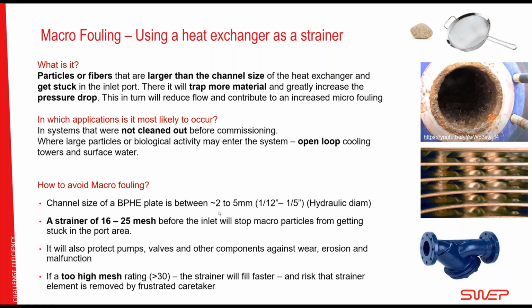As I mentioned, blockage is when the particle is too big for the channel size or the hydraulic diameter. The hydraulic diameter of a SWEP brazed plate heat exchanger is between 2 millimeters and 5 millimeters, or about a 12th of an inch to a fifth of an inch. That is the total distance over this one here. That is too big. So we recommend a strainer of about 16 to 25 mesh. 16 would be for the larger plate spacing and 25 mesh would be for the smaller plate spacing.